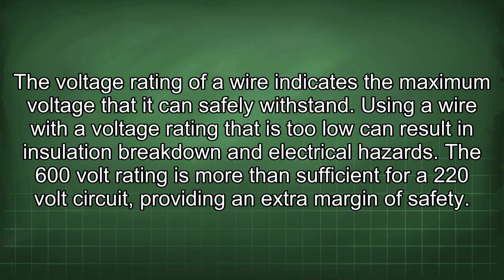The voltage rating of a wire indicates the maximum voltage that it can safely withstand. Using a wire with a voltage rating that is too low can result in insulation breakdown and electrical hazards. The 600-volt rating is more than sufficient for a 220-volt circuit, providing an extra margin of safety.